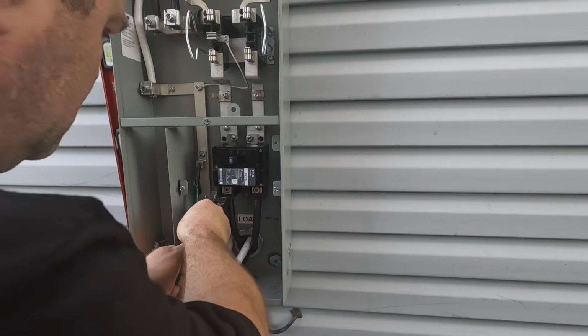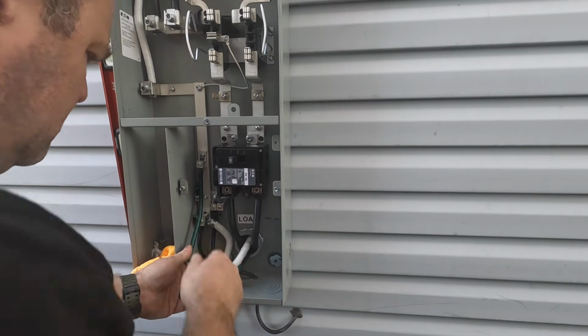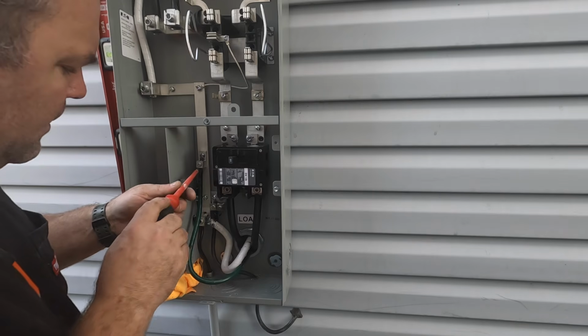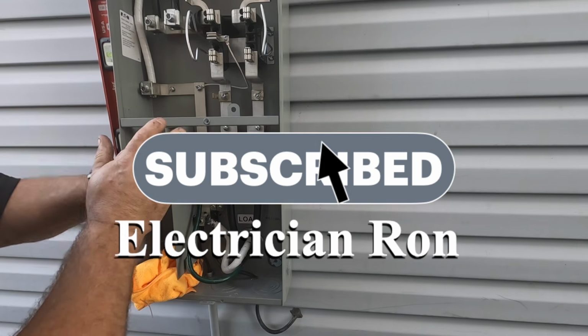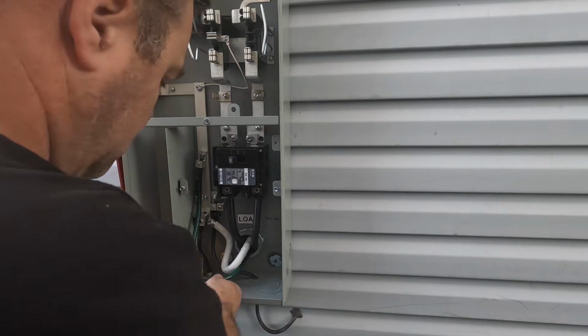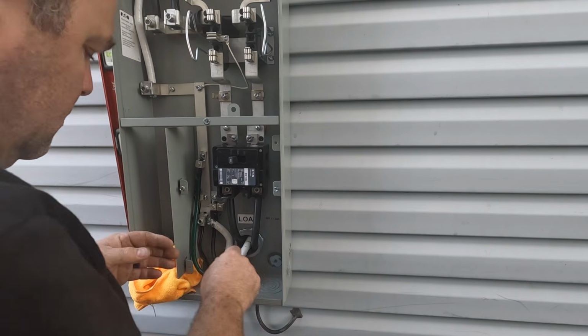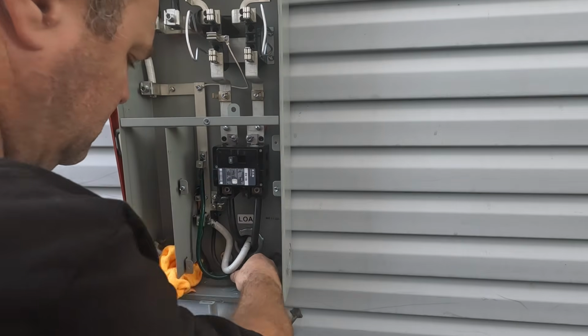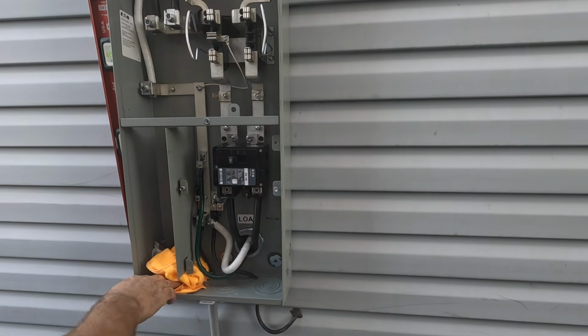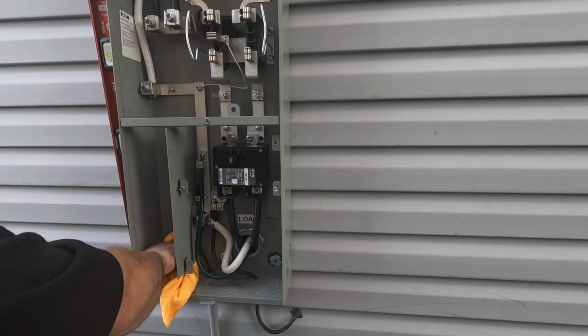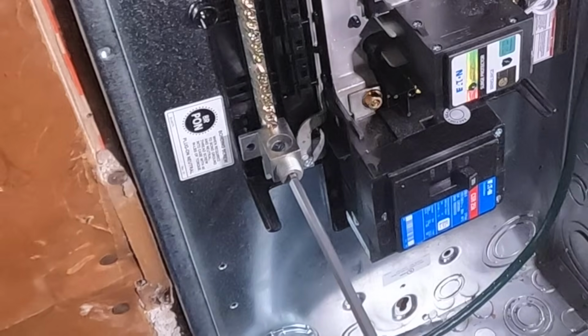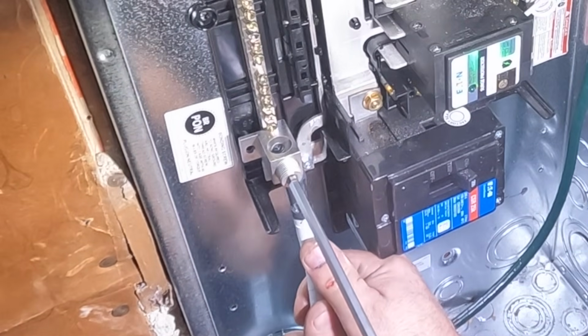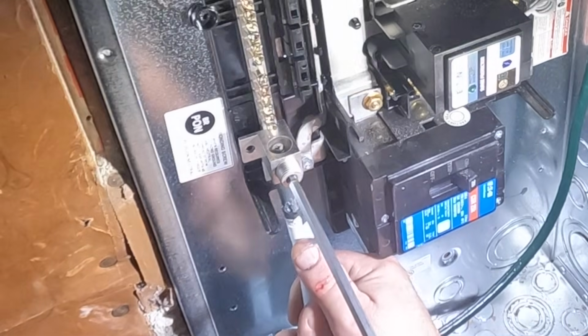Okay, so as is often the case here, there's a lot of grounding going on, and so I sometimes use a double lug to connect all my grounding electrode conductors and my equipment grounding conductor, my grounded neutral conductor. I just have to tap into that neutral bus with threads, and I use a 1/4-20 bolt to attach a ground lug directly to the bus of the grounded neutral from the service. This is also where the equipment grounding conductor is derived from. This right here is my grounded neutral wire. This is from the service.